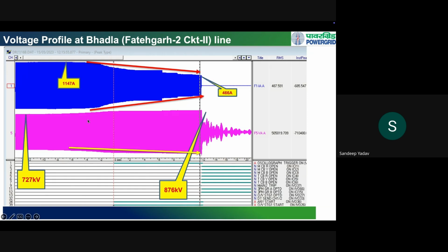this is what is happening, whenever there is a fault taking place, the voltage rises. If you look at this yellow line, the voltage rises steadily from the pre-fault voltage of 727 kV to 876 kV, a rise of more than 100 kV in the entire region, and this is because of the change in active power after the fault. The pre-fault current was over 1000 ampere, and it reduces as soon as the fault happens, and comes down to 466 ampere.